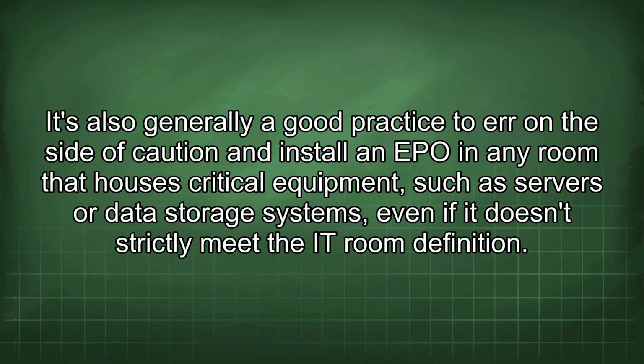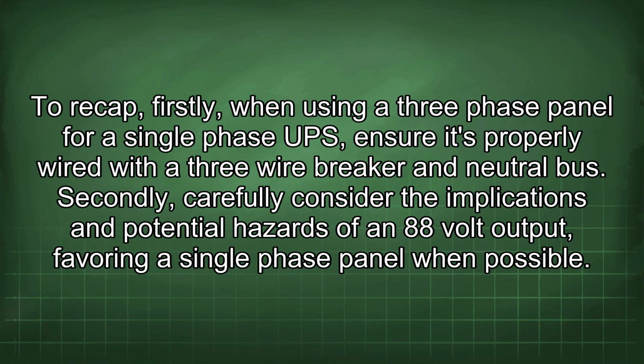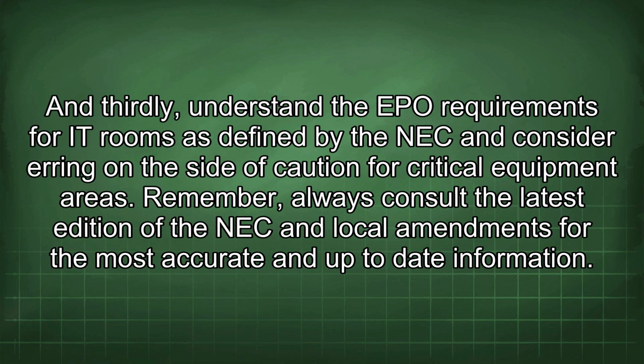of an IT room. It's also generally a good practice to err on the side of caution and install an EPO in any room that houses critical equipment, such as servers or data storage systems, even if it doesn't strictly meet the IT room definition. To recap, firstly, when using a three-phase panel for a single-phase UPS, ensure it's properly wired with a three-wire breaker and neutral bus. Secondly, carefully consider the implications and potential hazards of an 88-volt output, favoring a single-phase panel when possible. And thirdly, understand the EPO requirements for IT rooms as defined by the NEC and consider erring on the side of caution for critical equipment areas.